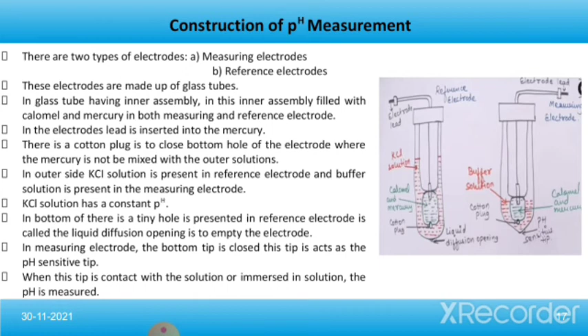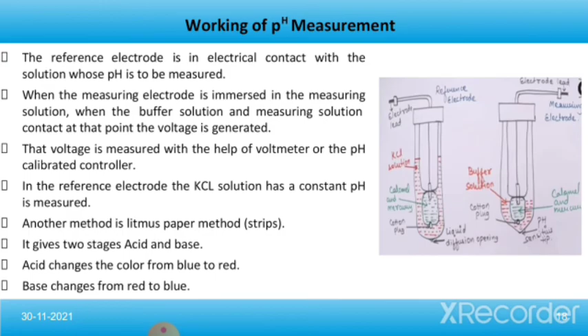Now we'll talk about the working of pH measurement. The reference electrode is in electrical contact with the solution whose pH is to be measured. When the measuring electrode is immersed in the measuring solution, and the buffered solution and the measuring solution come into contact, at that point a voltage is generated. That voltage is measured with the help of a voltmeter or the pH calibrated controller. In the reference electrode, the KCl solution has a constant pH. Another method for pH measurement is the litmus paper method. It gives two results, acid and base. Acid changes the color from blue to red and base changes the color from red to blue. So this is all about the working and construction of pH measurement.